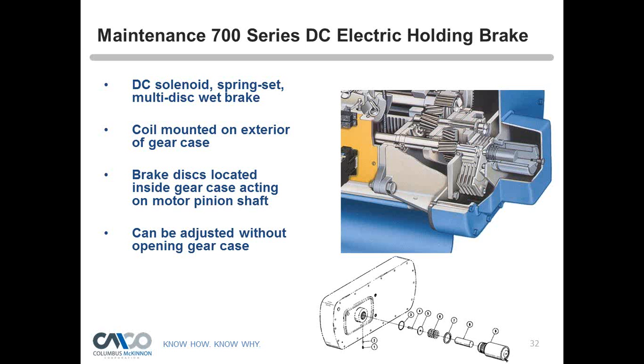On the shop star, you'll be looking for a rectifier, like I said, and you won't see it. They're very small diodes, but if you look closely at the contactor on the shop star, you will see black wires, and in the center of the wire, it's real fat, and that's the diode. That's basically the rectifier for the shop star. You'll see two of those, and then you'll also see a little surge protector that's put on the shop star because it comes right off the motor, so that the current doesn't damage the diodes. So anyway, just food for thought there.